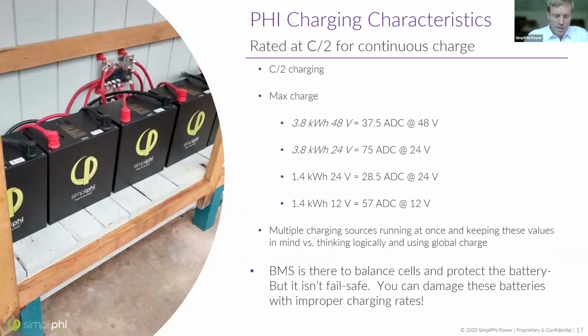Okay, so we rate our batteries at a charge rate of C/2. What that means is the capacity of the battery in 2 hours, all right? So if you have a 3.8 kilowatt hour battery, that's what our 48 volt Phi battery does, 75 amp hours of storage. If you divide that by 2 hours, then you would get 37.5 amps as the max charging rate.